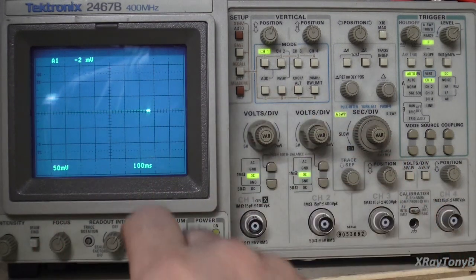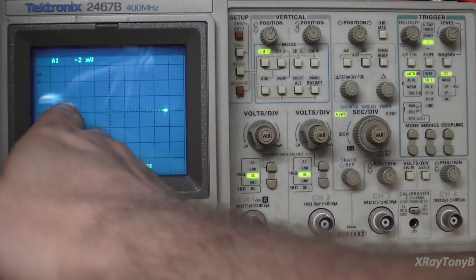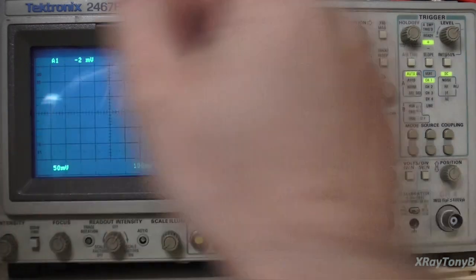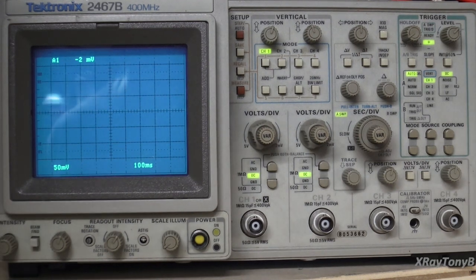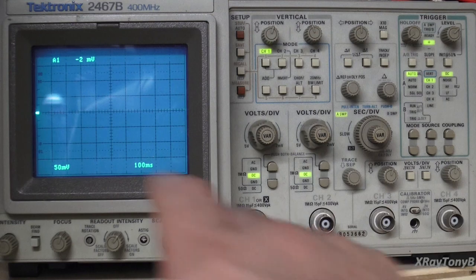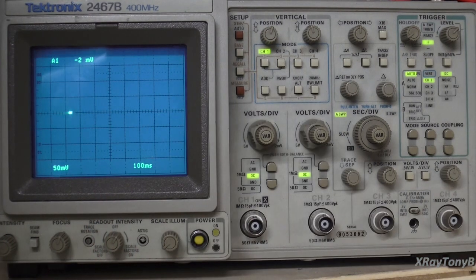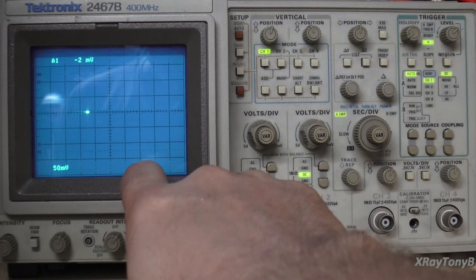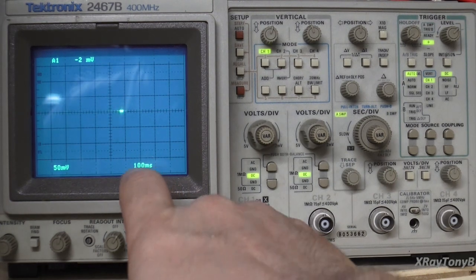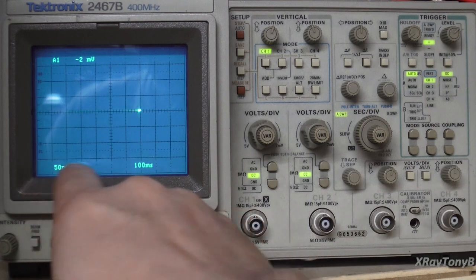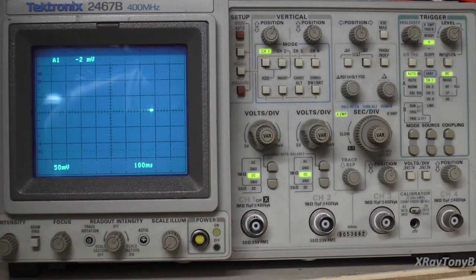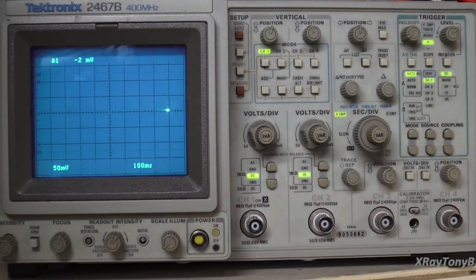If you look at that little trace dot, for it to go from this end of the graticule to this end, in other words, for it to move one division, it takes 100 milliseconds. So if we count all the divisions, 1, 2, 3, 4, 5, 6, 7, 8, 9, 10, it should take 10 of those 100 milliseconds to get from this side of the screen to this side exactly. So if this is 100 milliseconds per division and we have 10 divisions, it should take a total of 1 second, which is 10 times 100 milliseconds. 100 milliseconds is 0.1 of a second. So 0.1 times 10 is 1. So it would be 1 second to go from here to here.